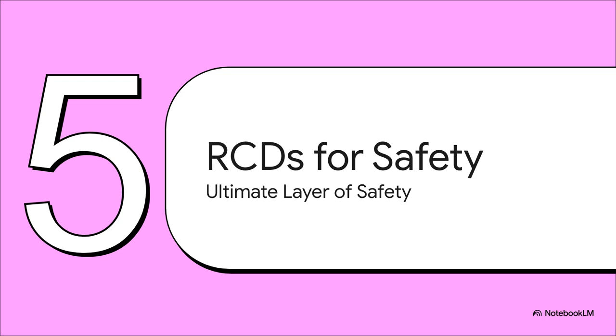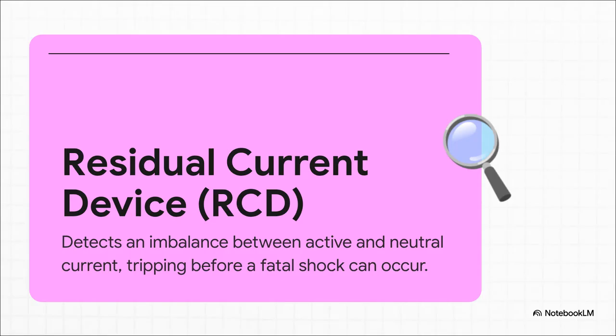We've now protected our wires from melting and our switchboards from exploding, but the final, and without a doubt the most important layer of safety is all about protecting people. And that is the specific job of the residual current device, or RCD. Now, it's so important to get this right. An RCD's job is not to stop you from getting an electric shock. It can't do that. Its job is to make sure that shock doesn't kill you.